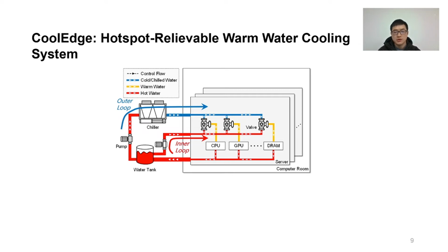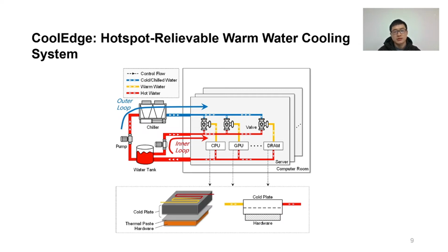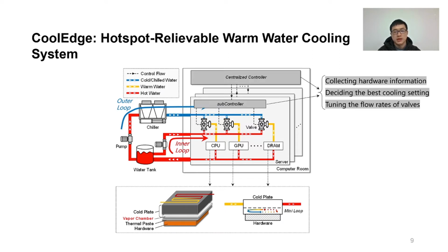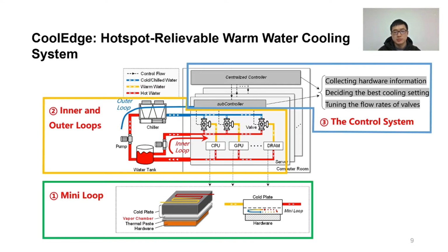To disperse hotspots inside a component, we integrate vapor chambers into cold plates that realize a vapor fluid mini loop. The vapor chamber can not only lower the overall hardware temperature, but also reduce local hotspots by smoothing the temperature distribution. We also design a control system that collects real-time hardware information, decides the best cooling setting, and implements the setting by tuning the flow rate of each valve. Next, we will introduce the mini loop, inner and outer loops, and the control system separately.